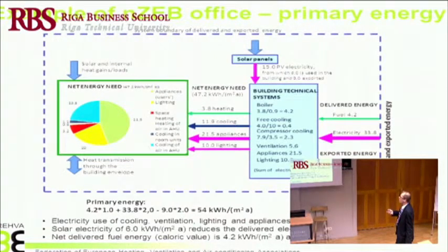At 90% efficiency, this gives you the amount of natural gas needed. When you calculate all electricity needs: free cooling was calculated with a COP of 10, so very little electricity is needed. Compressor cooling with a COP of 3.5 needs a bit more. Ventilation was given, appliances is a fixed value, and lighting doesn't change here. The sum of all electricity use is 39.8.